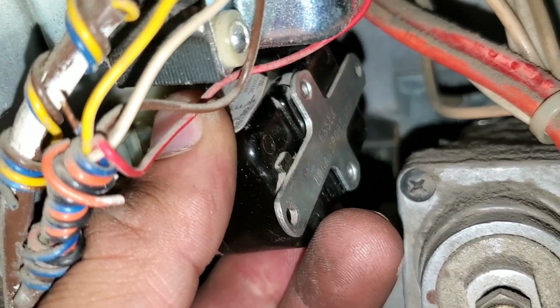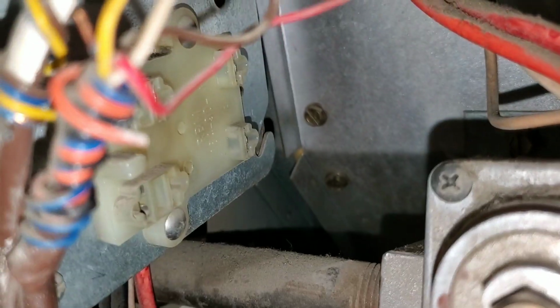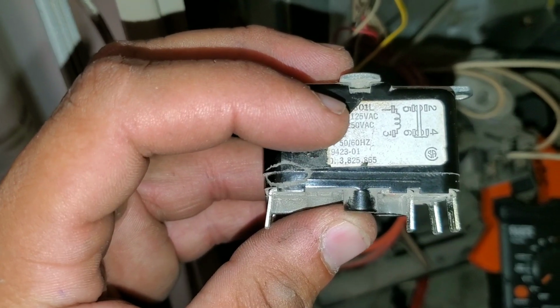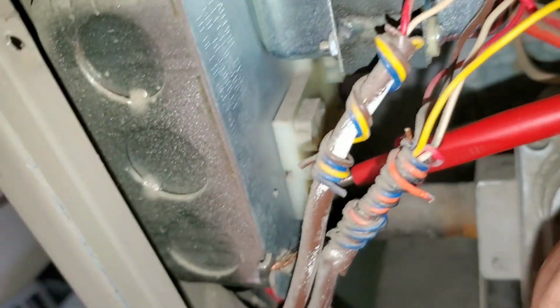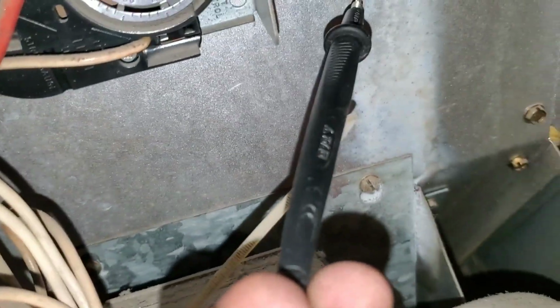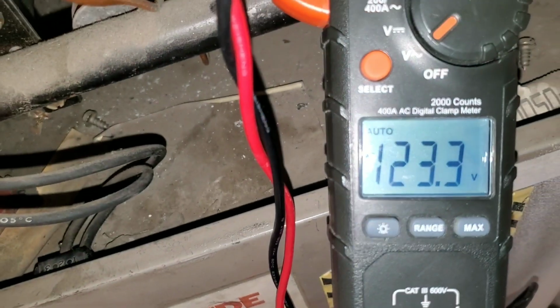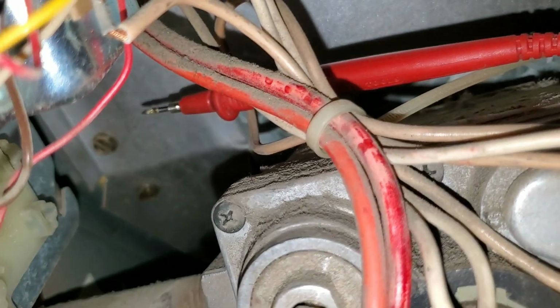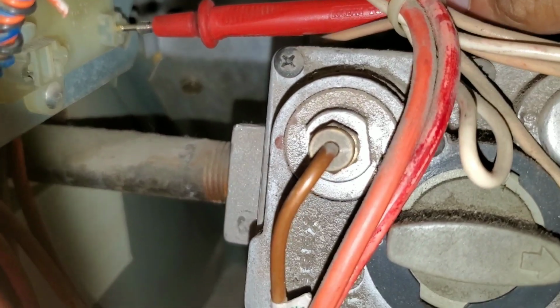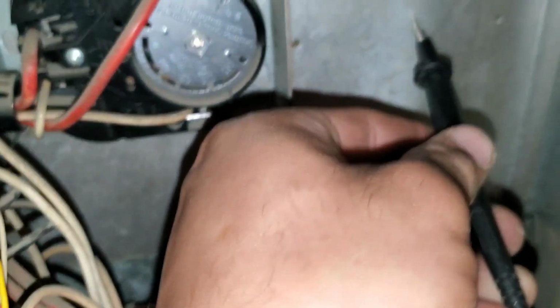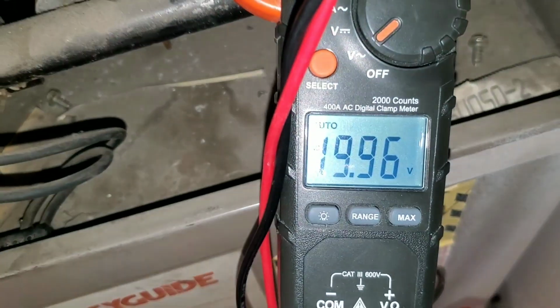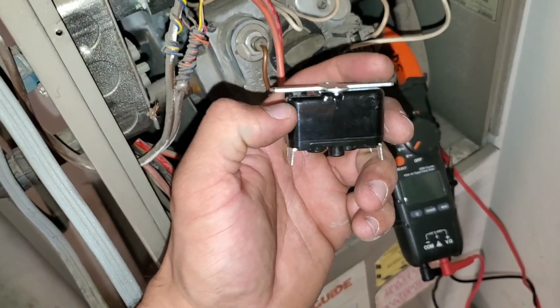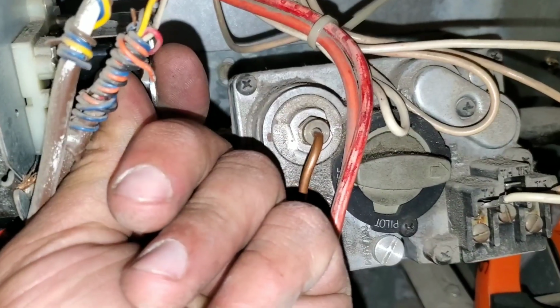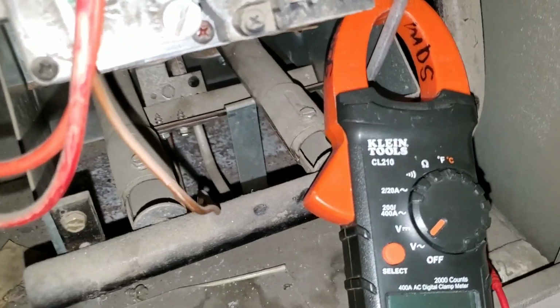Here I'm going to remove my fan relay, and I'm going to make sure that I am getting voltage. Now this one is energized with 120 volts, so we're going to test for 120 volts. And you can see here, I'm just setting one of my multimeter leads inside of the prong where my fan relay would go, and I have the other set to ground here, and I do have 120 volts. Now I'm also going to test for low voltage, so I'm going to insert one of my leads where my fan relay engages, and I'm just putting the other to ground here. Anywhere will be fine, and I do have low voltage. I do have a replacement fan relay, and we're going to go ahead and put that in. You can see as soon as I put the new relay in, my blower motor did turn on.